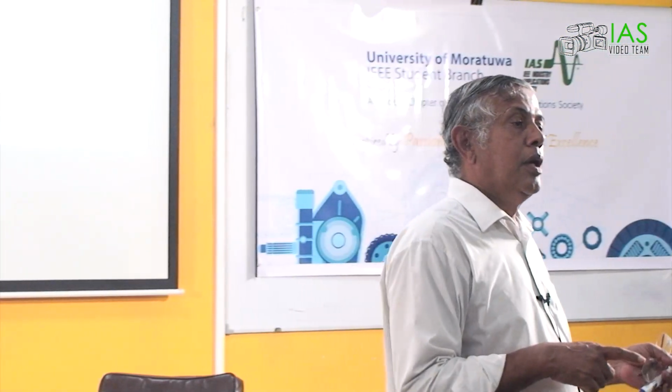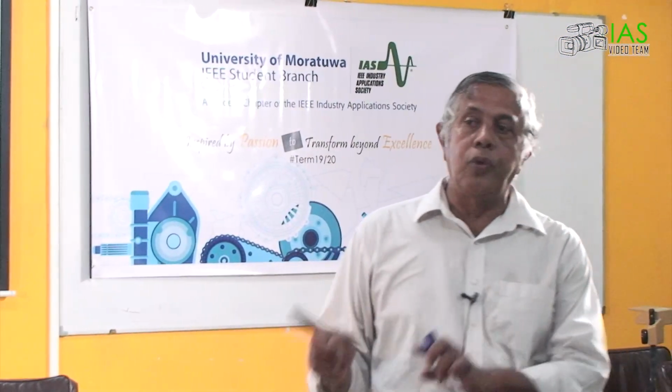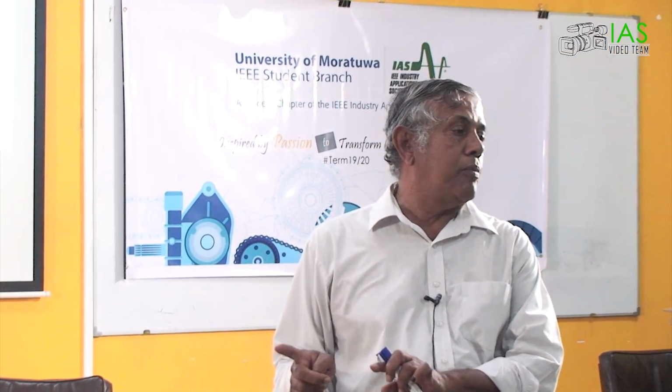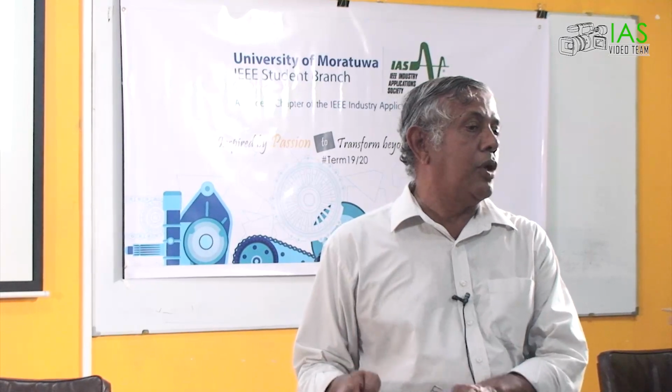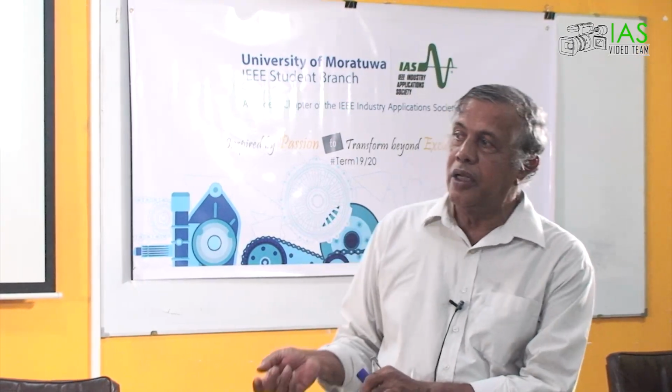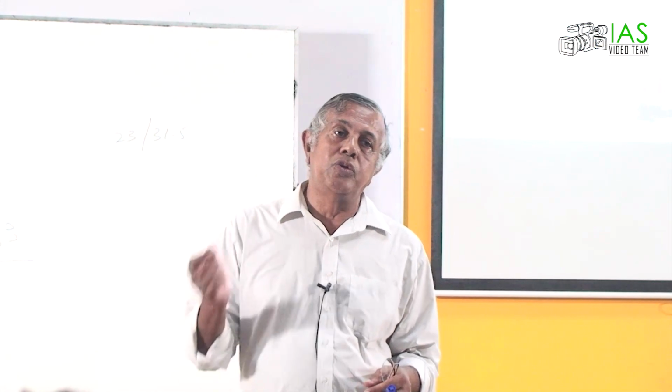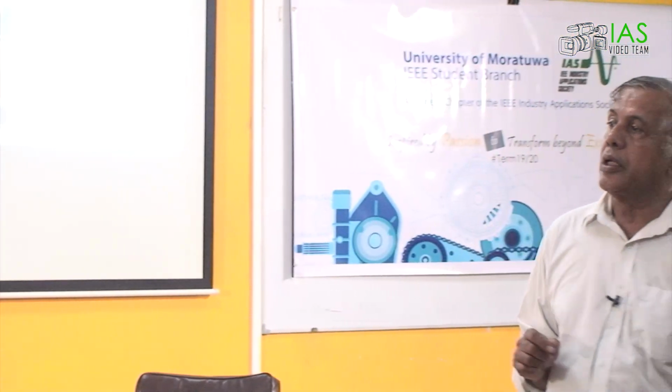Now, inside the building, are you allowed to put a mineral oil filled transformer? You are not, because that has combustibles. The transformer oil burns easily and it can catch fire and damage the building. So you are not supposed to put an oil-filled transformer inside a building.